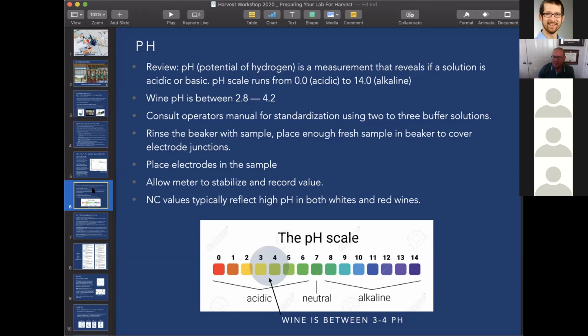You should really have a conical or a spherical probe. When you're thinking about the probe, it's got a round bulb on the bottom. There's a junction point right above that round bulb. That's very important because part of this internal solution will leak out and create your pH reading, based off of what the internal solution is, and also the calibration standard that you establish. You want to make sure that your pH probe is under the surface of the sample, under the junction point.